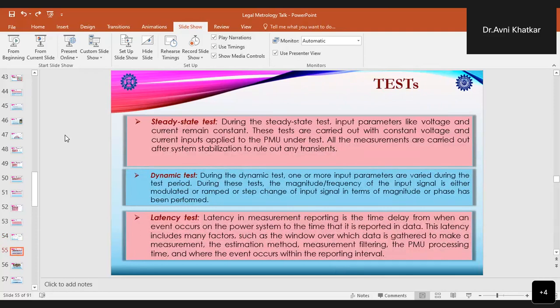When we talk about the tests for the PMUs, we undergo different types of tests. Basically, they are divided into three categories, that is steady state test, dynamic test, and the latency test. In the steady state test, the input parameters like voltage and current remain constant. These tests are carried out with constant voltage and current inputs which are applied to the PMU under test. All the measurements are carried out after the system stabilization, in order to rule out any transients, because we are talking about the steady state test.